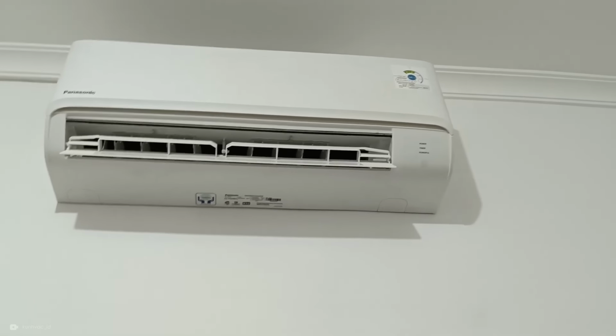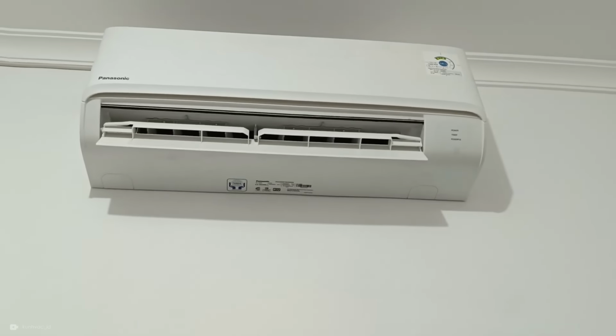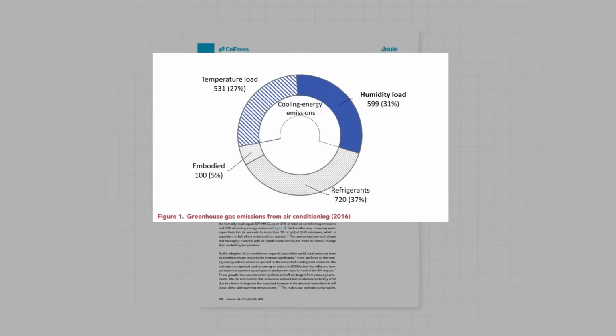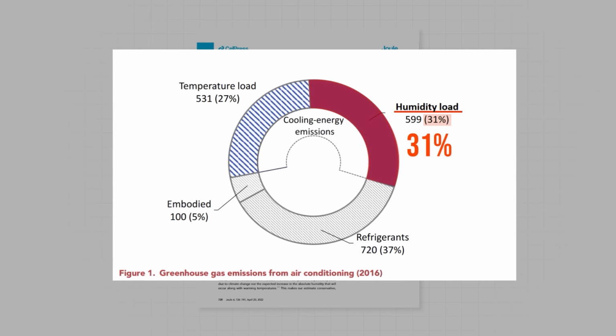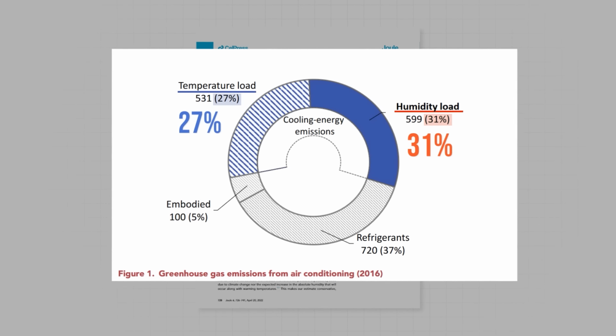This phase change from vapor to liquid is energy intensive, and there's some fascinating research that shows this humidity load results in more emissions than the temperature load. That is to say, we're emitting more CO2 by taking water out of the air than cooling it, which is the whole point of the process anyway.